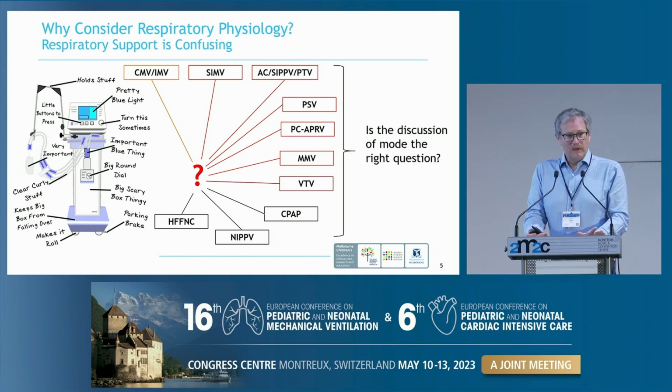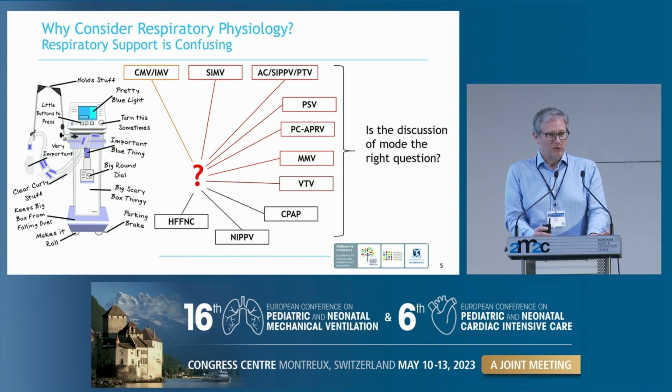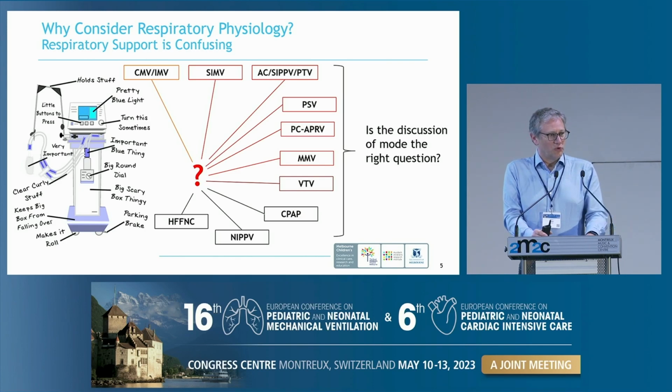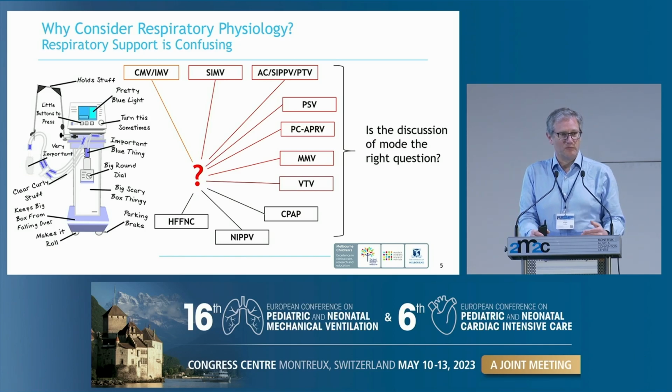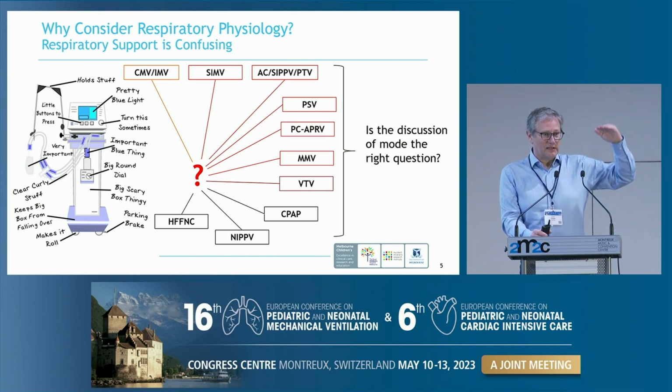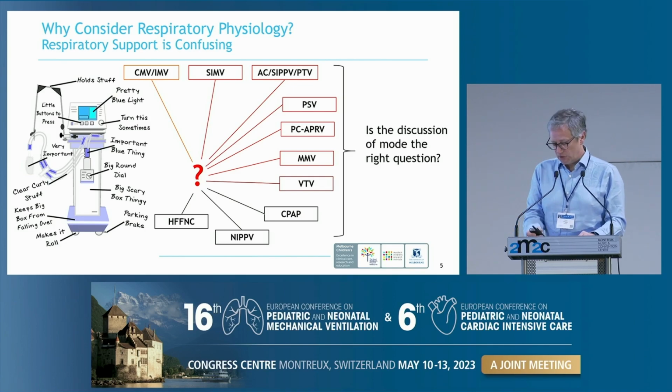In a neonatal ventilator, all of our modes, essentially, there are some exceptions on some ventilators, are time-cycled pressure-limited ventilation or flow-cycled pressure-limited ventilation. And I think that's really important. If you're using volume control, when we talk about volume targeting, which I'll talk about in a minute, we're essentially still talking about time-cycled pressure-limited ventilation. We're just allowing the ventilator to be involved in how it changes pressure to deliver volume.